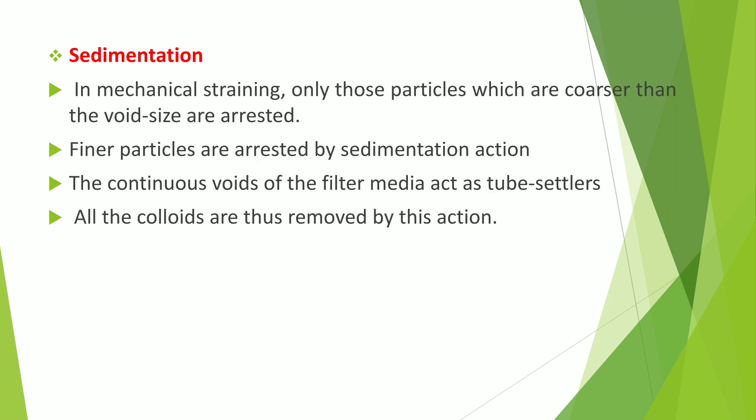Next, as water passes down further, the sedimentation process starts. In mechanical straining, only those particles coarser than the void size are arrested; finer particles are arrested by sedimentation action. The continuous voids of the filter media act as tube settlers, and all the colloids are thus removed by this action. As explained in the previous video about how tube settlers work, similarly, the void spaces present in the filter media act like tubes and help with sedimentation.